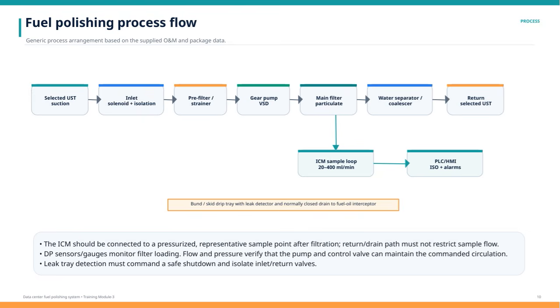An important part of the system is the ICM sample loop, which takes a small, controlled sample of fuel, between 20 and 400 milliliters per minute, for analysis. This sample point is pressurized and located after filtration, so the fuel analyzed is representative and clean. The entire process is monitored and controlled by a PLC and HMI system, which includes isolation and alarms to ensure safe operation. There's also a bund or skid drip tray equipped with a leak detector and a normally closed drain valve that leads to a fuel oil interceptor.